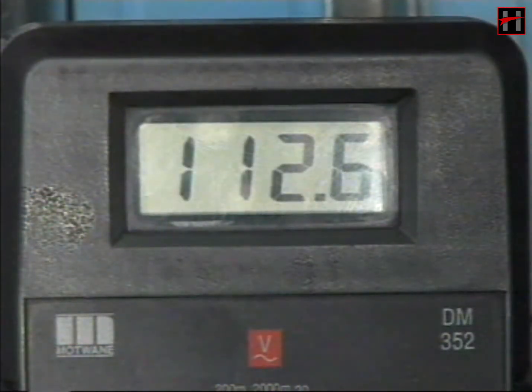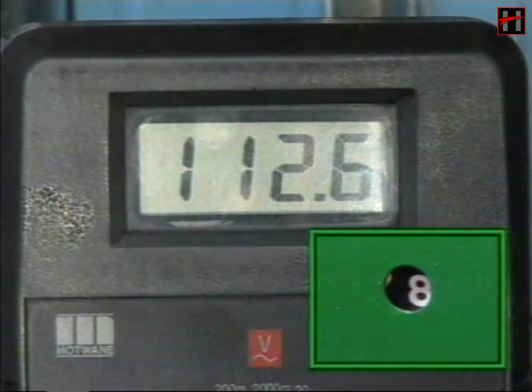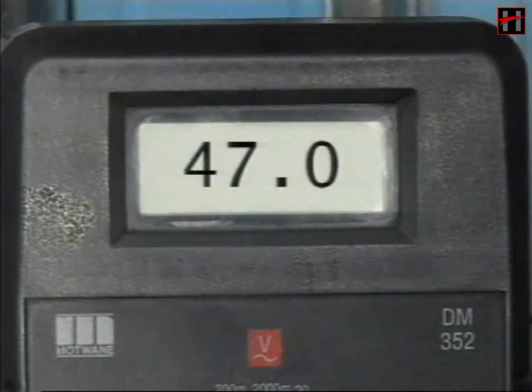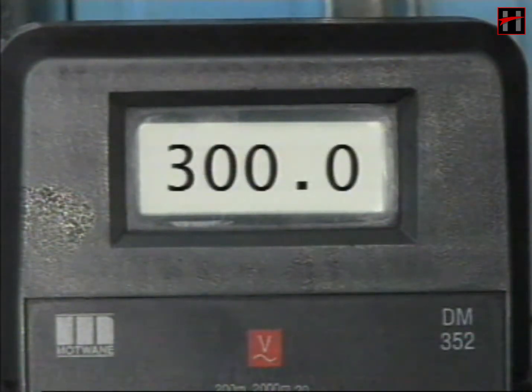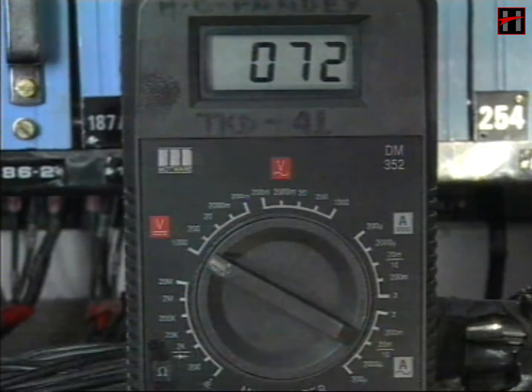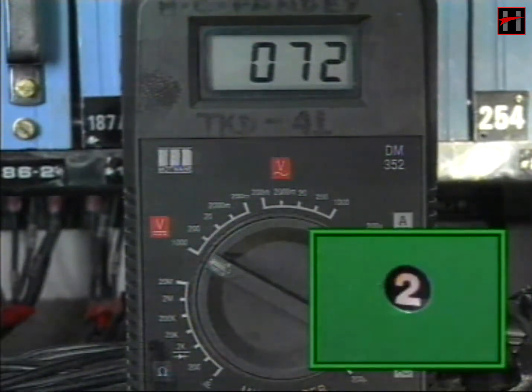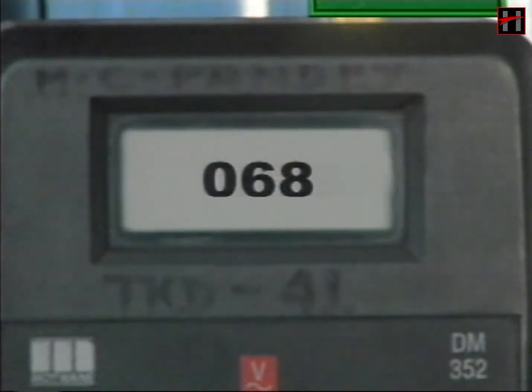The tacho generator voltage should be 105 to 115 volts on 8th notch and 45 to 50 volts on idle. The millivolt drop in the series combination should not be more than 300 millivolts, and the millivolt drop in parallel combination should not be more than 100 millivolts. The battery charging voltage should be 72 volts approximately, plus minus 0.5 volts on all notches. The battery voltage should be 68 volts.